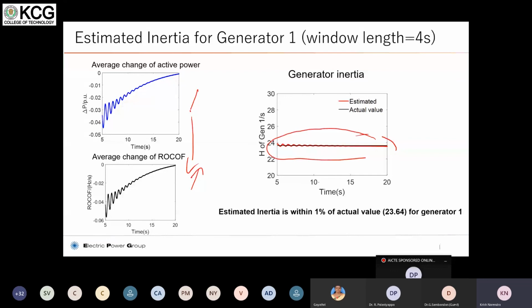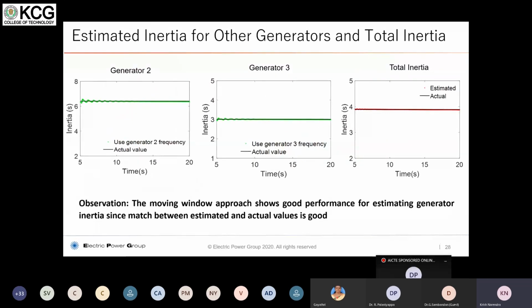Within 10 seconds after the disturbance, the value converged to 23.64, which is very close to 24, the design value of the inertia of the system, within 1% of the actual design value. The estimated inertia for the other generators and the total inertia is also shown here, and it agrees very well with the window of 4 seconds.